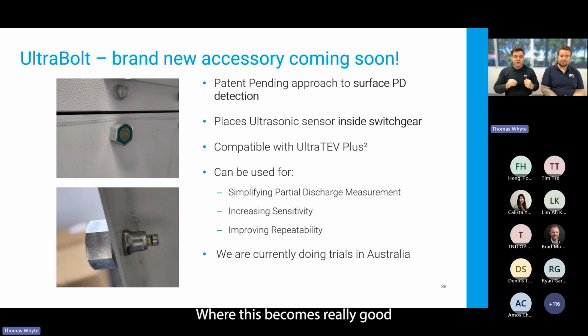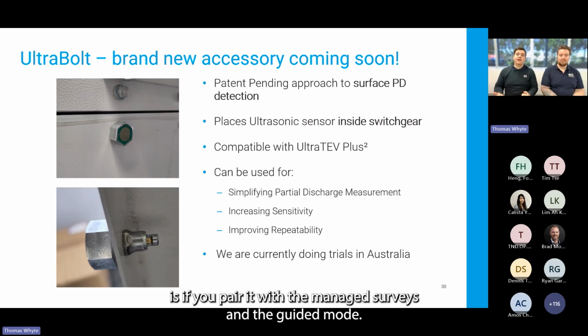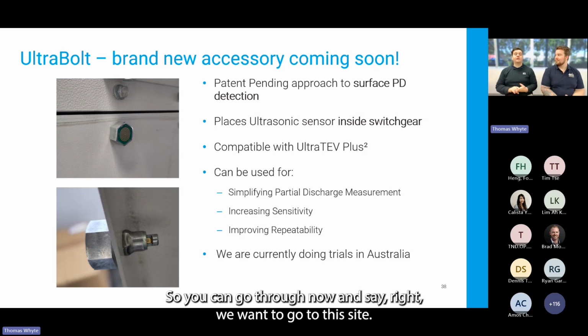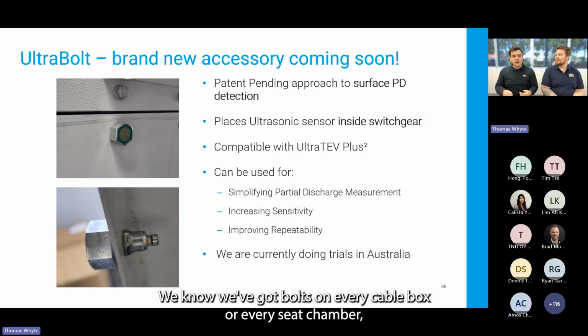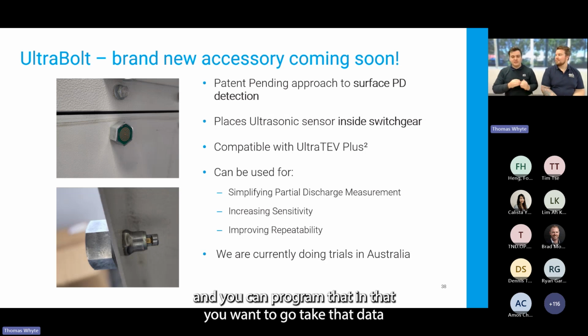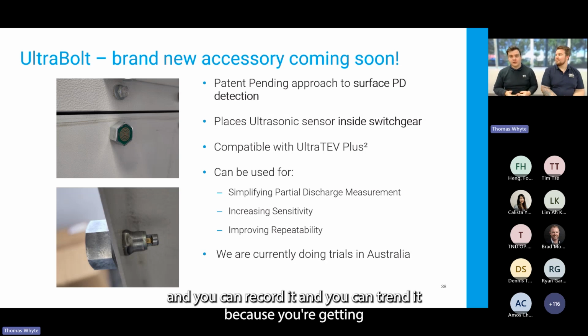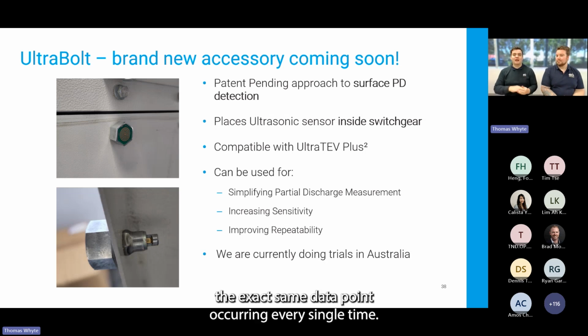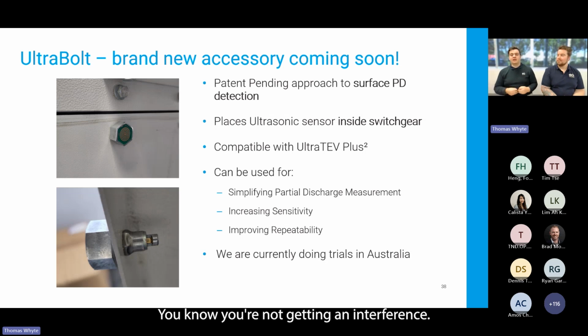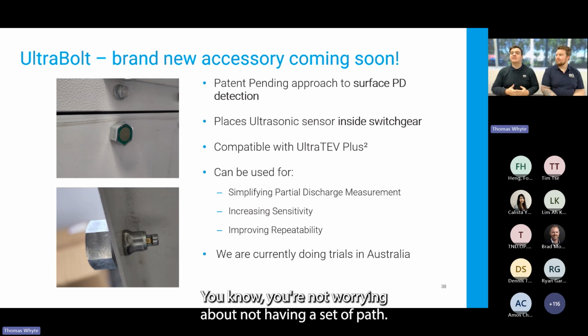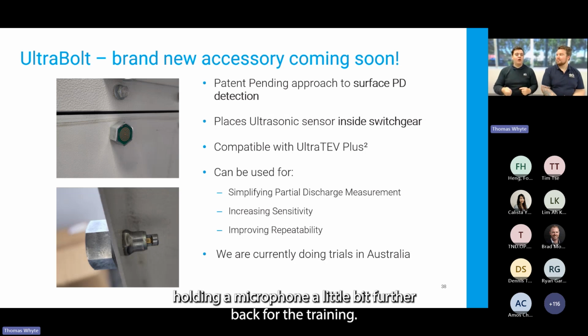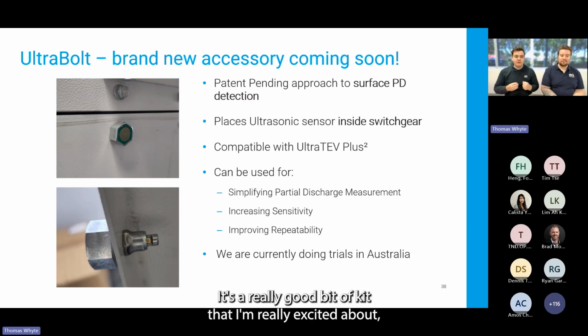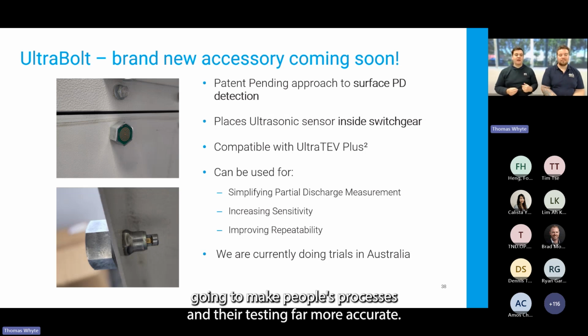Where this becomes really good is if you pair it with managed surveys and guided mode. You can say we want to go to this site, we know we've got bolts on every cable box or every CT chamber, and you can program that in. You can record the data and trend it because you're getting the exact same data point every single time. You're not getting interference, not worrying about having a set air path, not worrying about one tester holding the microphone a little further back for the trending. It's a really good bit of kit that I'm excited about because I think it'll make testing far more accurate.